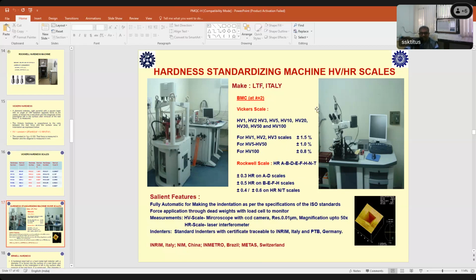This machine also has some Rockwell scales, as mentioned here, and these are some of the salient features of this machine. It is fully automatic for making the indentation as per the specification of the ISO standard. Force application is through dead weights with a load cell to monitor. Whenever you apply the force, it has to be properly monitored, whether you are applying the required force as per the standard. There shouldn't be any variation, and it should be within the limits.